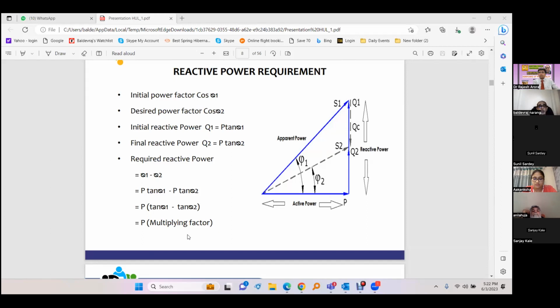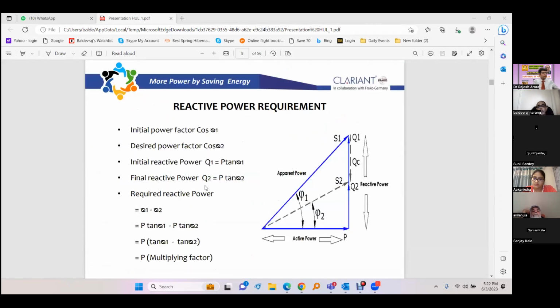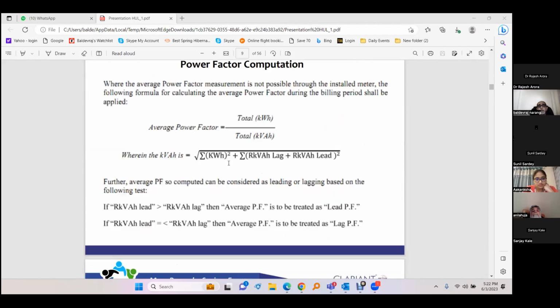And we don't always have to use this formula. We can just go to the chart, which is already made for all these conditions, and we can find out the requirements. So what is happening is, the average power factor was earlier the criteria for giving incentives on the power factor, and that was for the entire month, the average was calculated. And now the billing has gone to kVAH. So the power factor is not directly required to calculate the incentives available. So kVAH has got built-in incentives for the power factor.